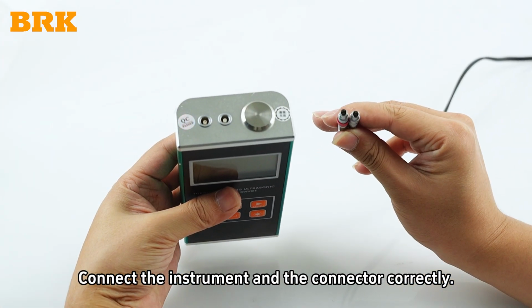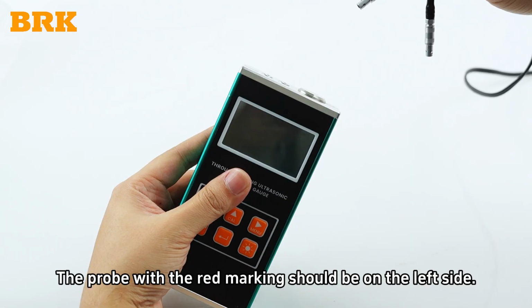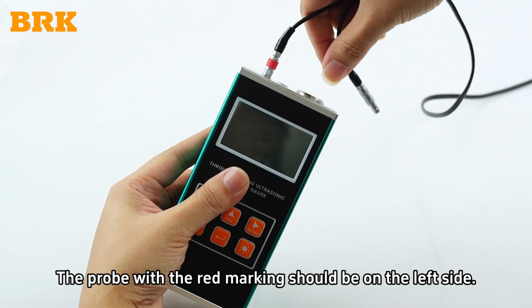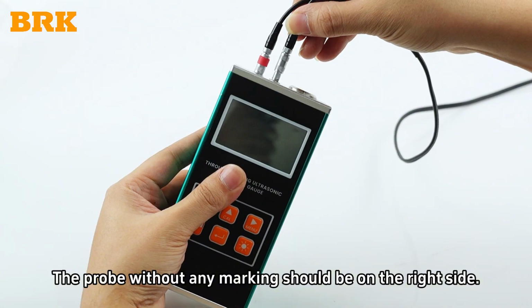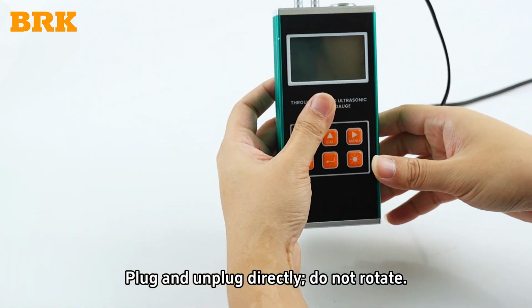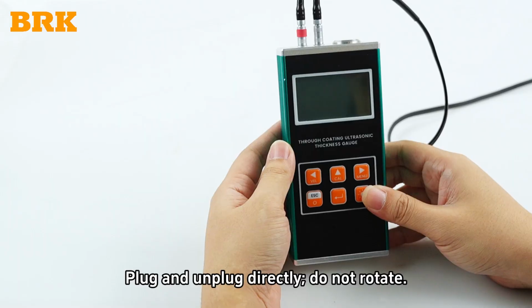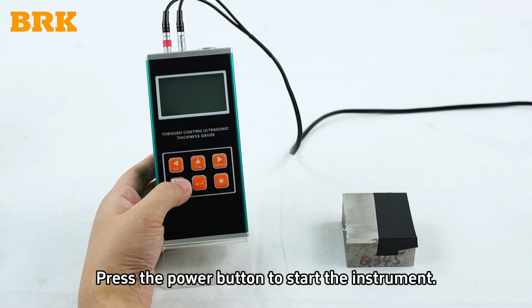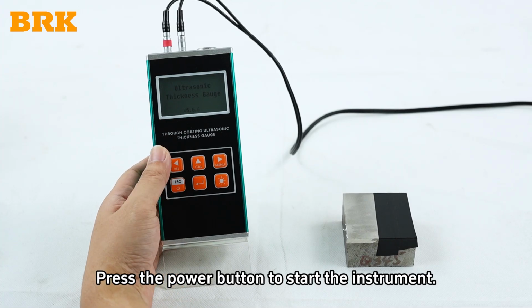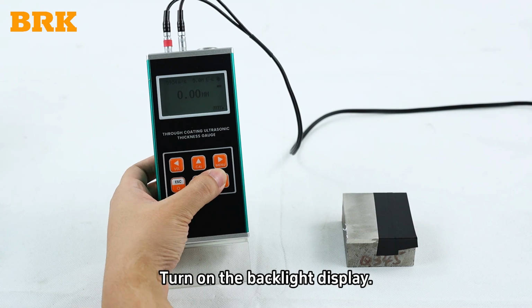Connect the instrument and the connector correctly. The probe with the red marking should be on the left side. The probe without any marking should be on the right side. Plug and unplug directly. Do not rotate. Press the power button to start the instrument. Turn on the backlight display.